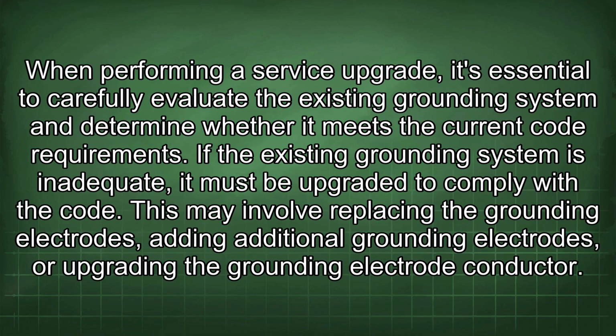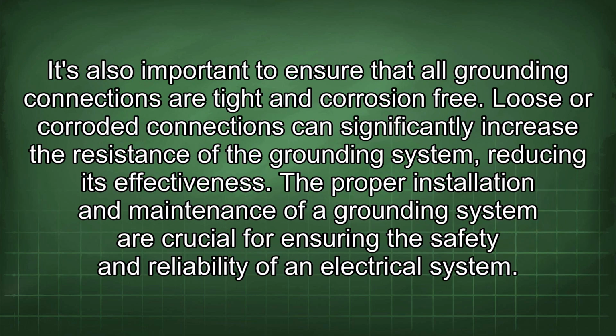ensure safety. When performing a service upgrade, it's essential to carefully evaluate the existing grounding system and determine whether it meets the current code requirements. If the existing grounding system is inadequate, it must be upgraded to comply with the code. This may involve replacing the grounding electrodes, adding additional grounding electrodes, or upgrading the grounding electrode conductor. It's also important to ensure that all grounding connections are tight and corrosion-free. Loose or corroded connections can significantly increase the resistance of the grounding system, reducing its effectiveness.